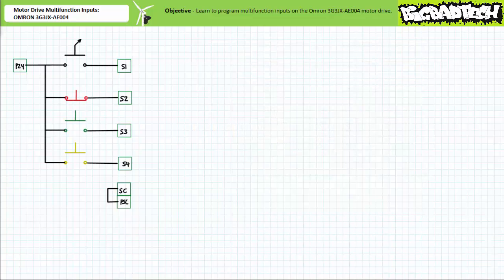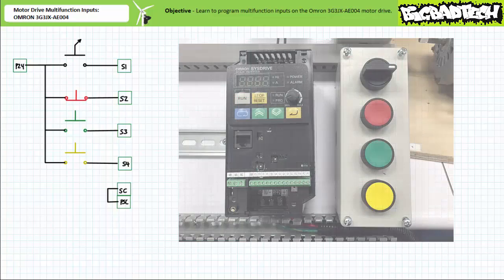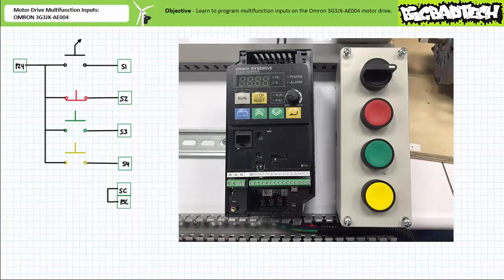Now let's wire up some inputs. For the purposes of this particular lecture, we'll only be making use of two input devices. However, to demonstrate other functions in later lectures, we'll wire up enough inputs to fill a four-hole push button enclosure. Let's use a normally open maintain contact selector switch as input 1, a normally closed momentary contact red push button as input 2, a normally open momentary contact green push button as input 3, and a normally open momentary contact yellow push button as input 4.